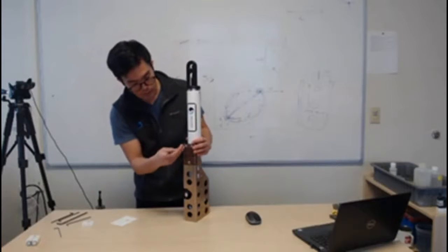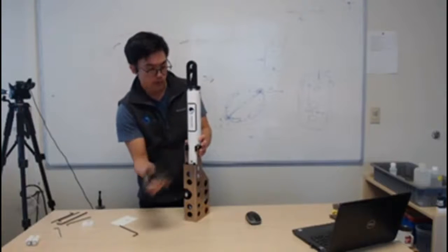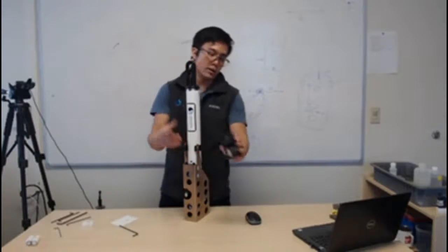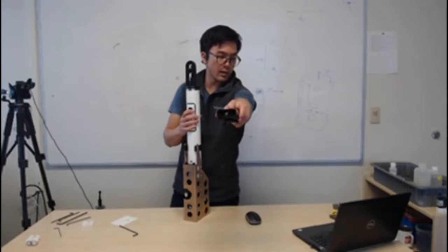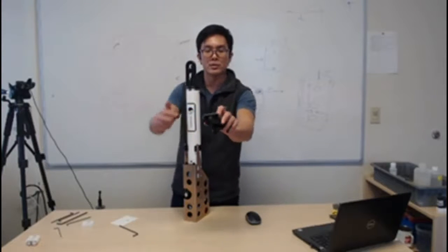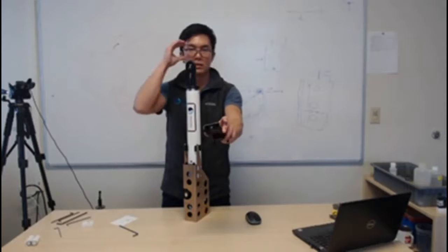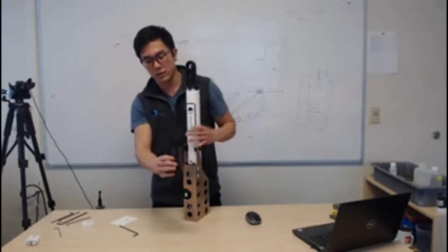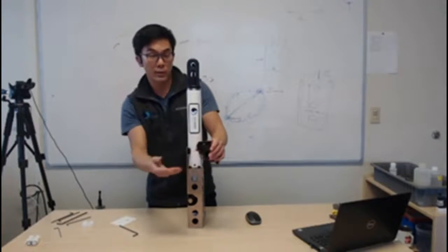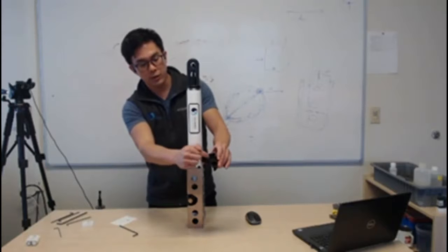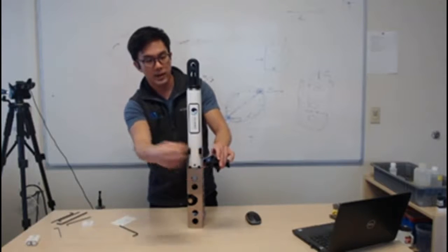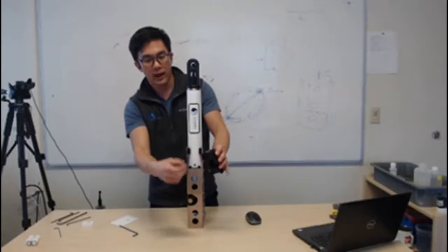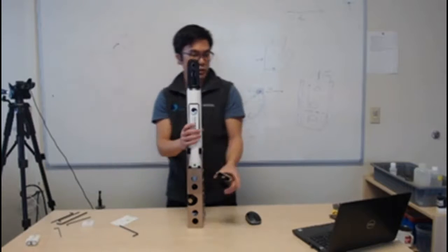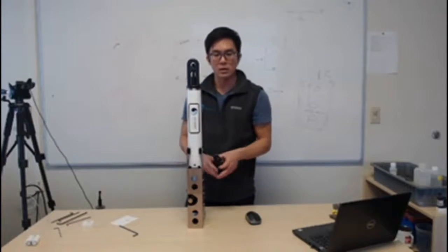Once they are completely loose, this comes right off. If you look inside of here, this might be kind of hard to see, but there are these two holes that house the antifouling chemicals, or the cartridges. If you need to replace those, you can remove this screw right here. This plastic piece comes right off, and then you can replace it with new cartridges, shown in the picture on the bottom right.